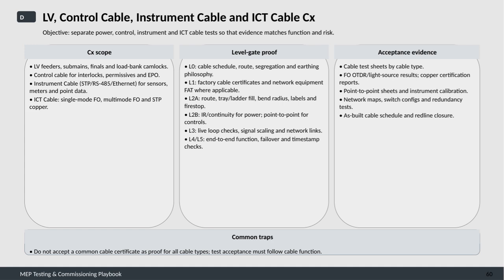L2B involves electrical tests, insulation resistance and continuity for power cables, and point-to-point verification for control cables. Level 3 then moves into live loop checks, signal scaling, and confirming network links. Finally, L4 and L5 consist of end-to-end functional testing, failover scenarios, and timestamp accuracy validations.